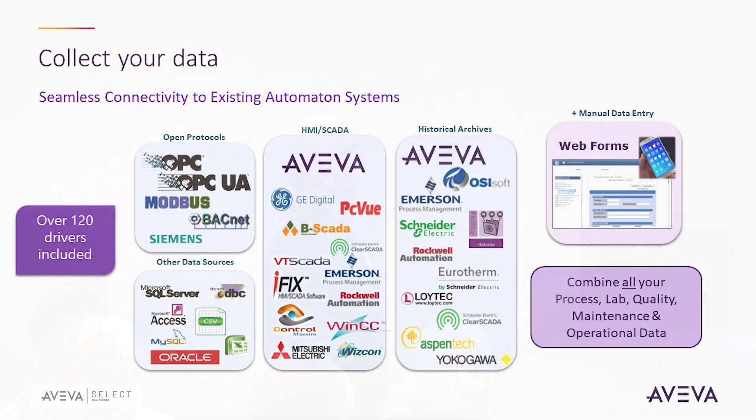Let's talk about collecting the data. We have over 120 different drivers included with the product — built right in with very little configuration. There are open protocols: OPC UA, Modbus. We have MQTT drivers that can collect data natively. SQL access lets you run SQL queries, all included with the unlimited packages. We also have HMI/SCADA data and historical archives, classic and new AVEVA products, OSI PI applications. We're including asset framework capabilities and working on event frame capabilities as well.